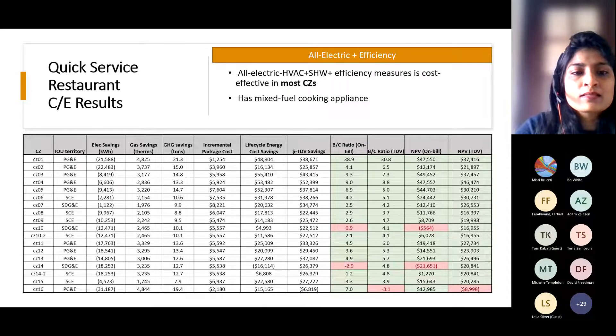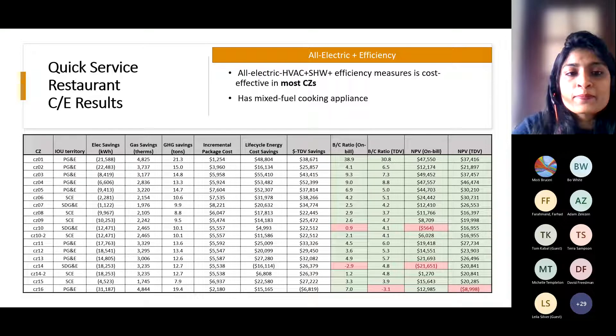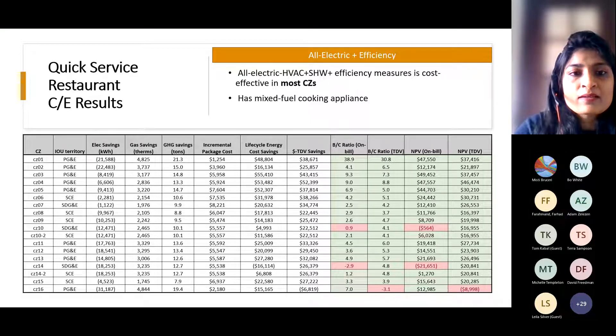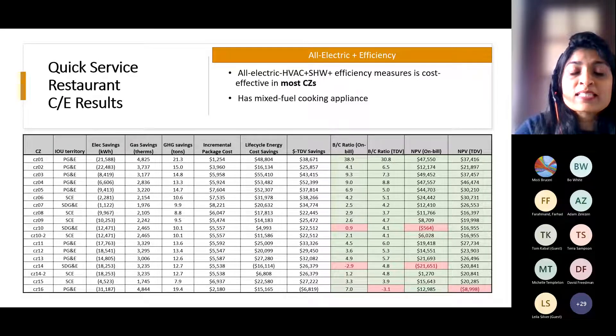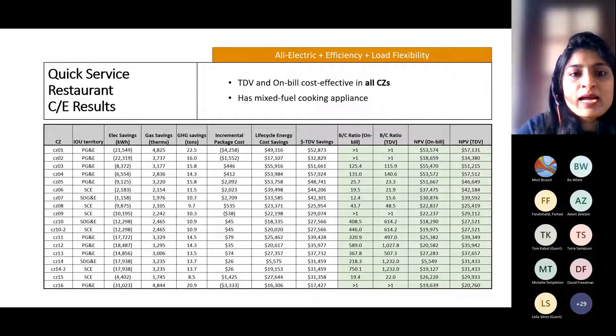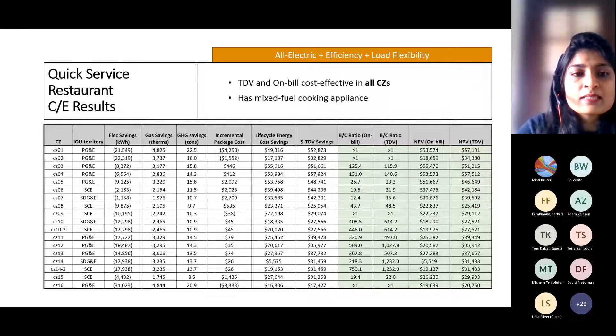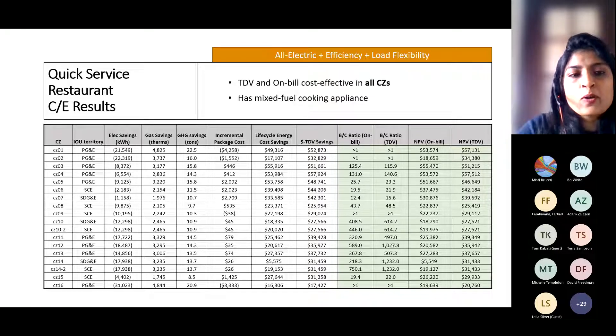Adding efficiency measures to the electrification package — HVAC and water heating only, with gas cooking in both baseline and proposed — improves on-bill cost-effectiveness and gives cost-effective results for almost all climate zones. So to answer Christine's question: there are reach code options that can be implemented for restaurants; it just means we need exemptions for cooking. We also added a load flexibility measure — load shifting in heat pump water heater by preheating before peak periods — and that package is cost-effective for all climate zones.